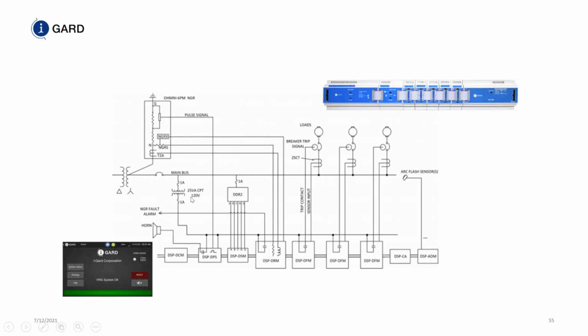But when you turn on the pulsing, we monitor the voltage on the bus, and because 1/3 of the time A phase has a fault, 1/3 of the time B phase has a fault, and 1/3 of the time C phase has a fault, all three phases contribute to the fault because it's a DC fault derived from an AC system, and because you have a 6-pulse rectifier at the front end of most variable frequency drives, we can detect the presence of that fault. When you turn on the pulsing, you actually create a change in flux, and the CT can detect that fault and tell you exactly where the fault is in which feeder.